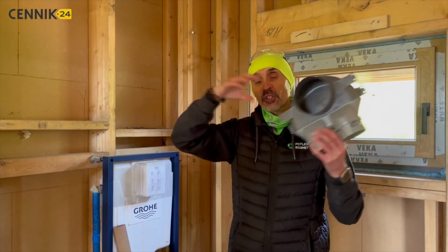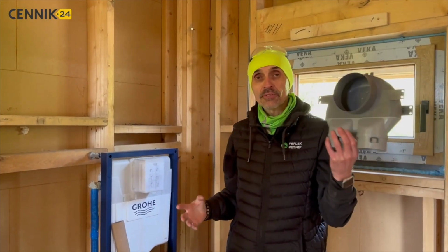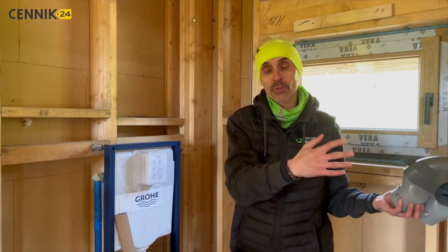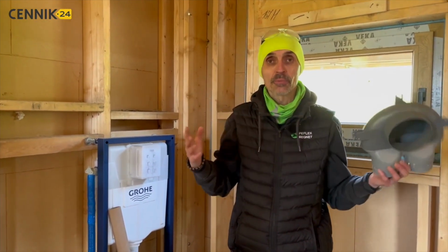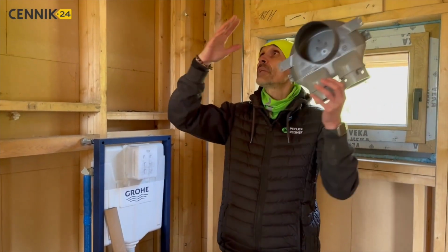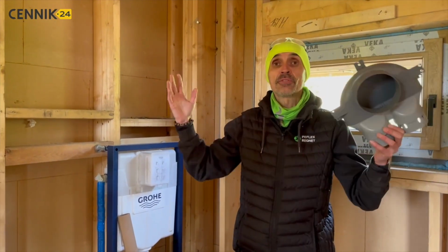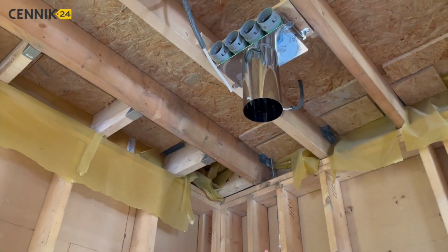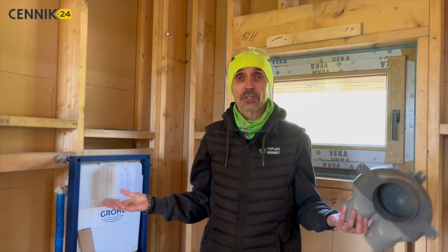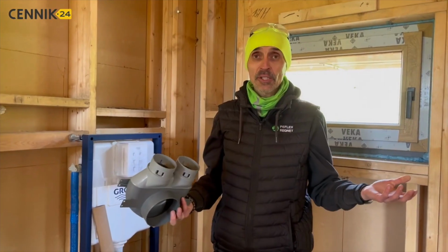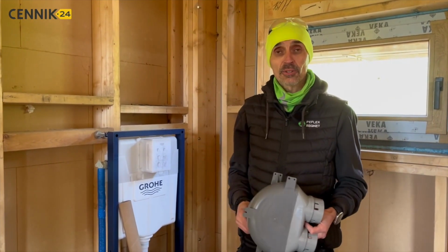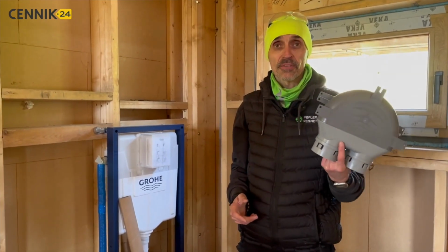In terms of air distribution, it's better to install 2 boxes so that the air spreads more evenly, for example, throughout the bedroom, the living room, or other rooms. However, due to the limited space on the ceiling, we can use a box like this one here, with a 160mm air diffuser, to extract and direct the right amount of air from here. So, I invite you to visit the Cennik24 website for more information about the boxes offered by Peflex.